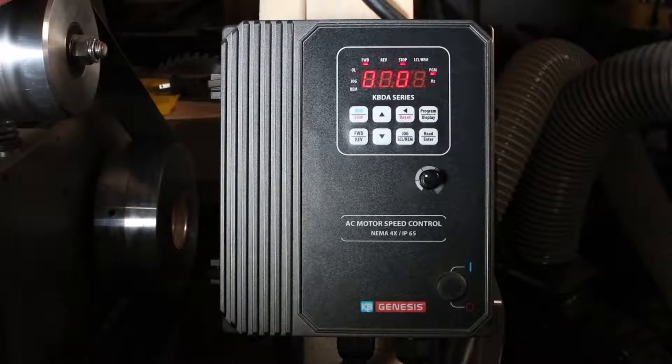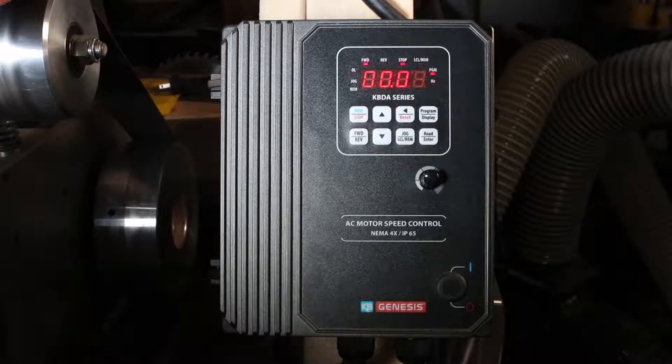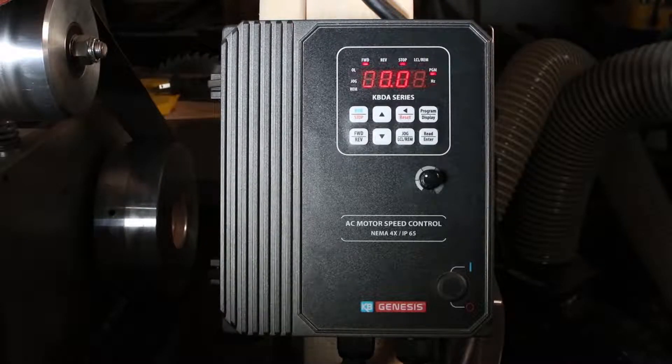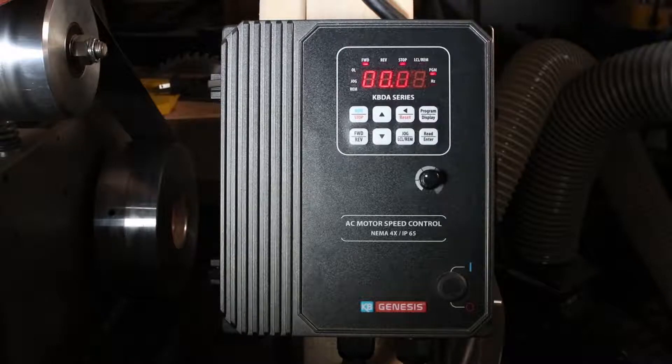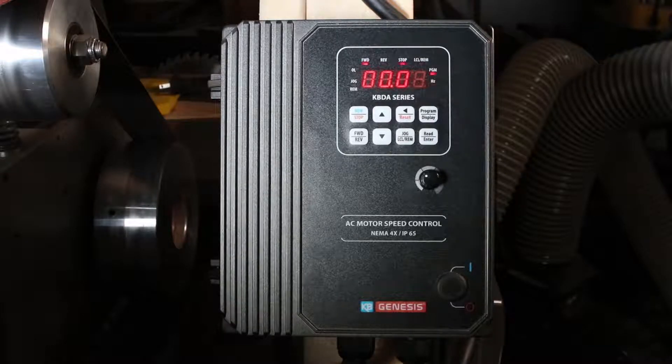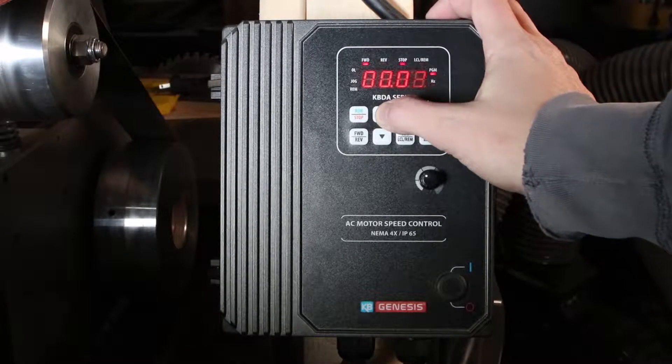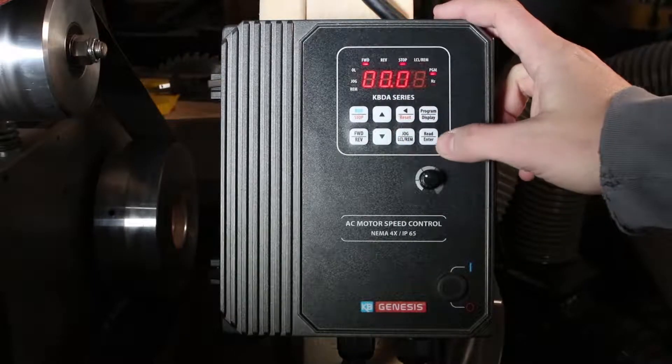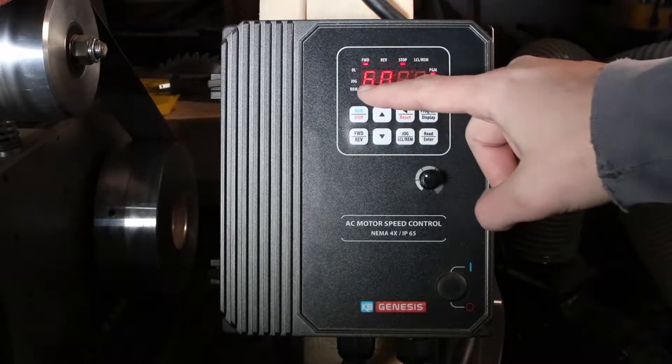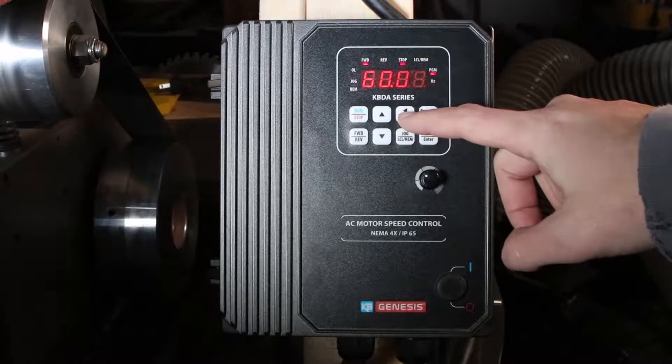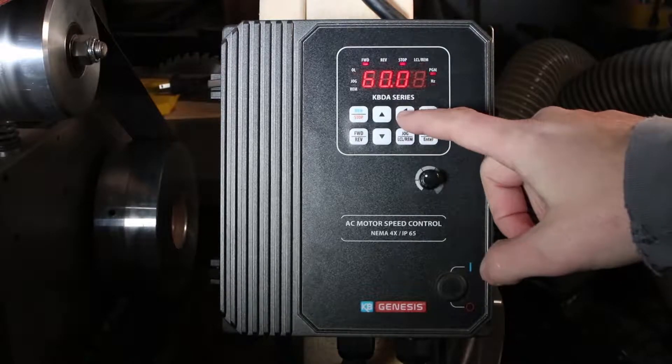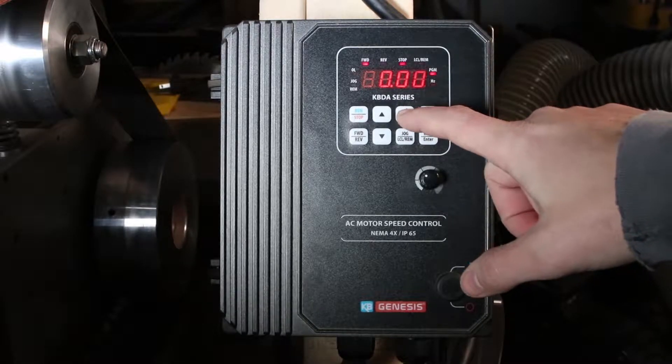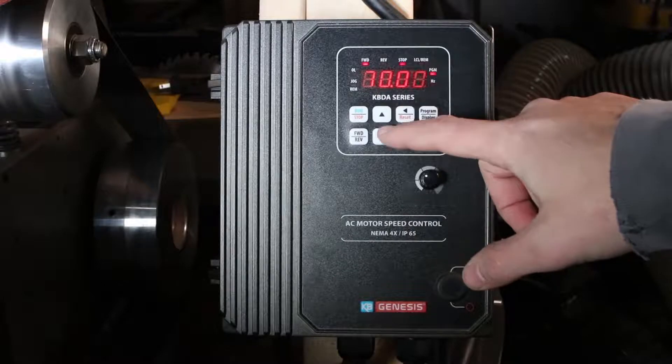So you have to also tell it what the maximum frequency is. So you would change option 005. Now it's at 60 right now, so you would have to change this to 120.